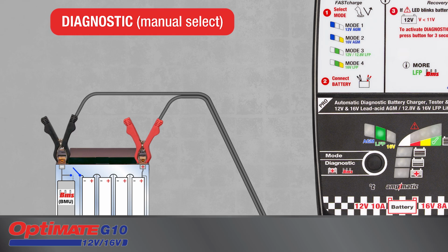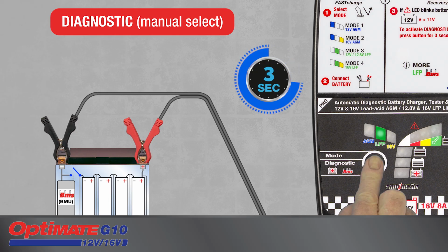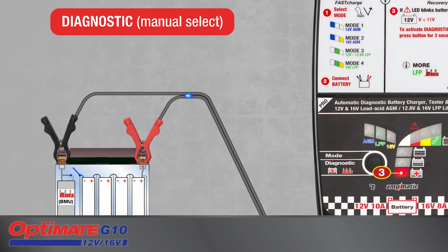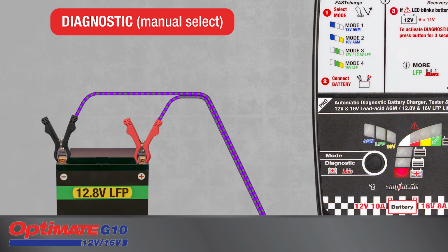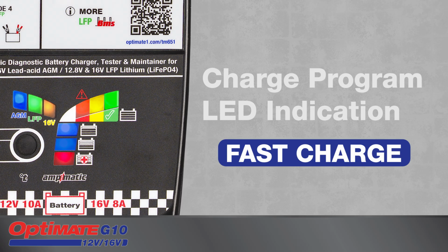Press the button for a further 3 seconds until LED 3 blinks, indicating BMS reset pulses are being delivered to the battery. When LED 3 turns full on, the battery's BMS has reset and is receiving charge. The LEDs are numbered from 1 to 8 as per the instruction manual.